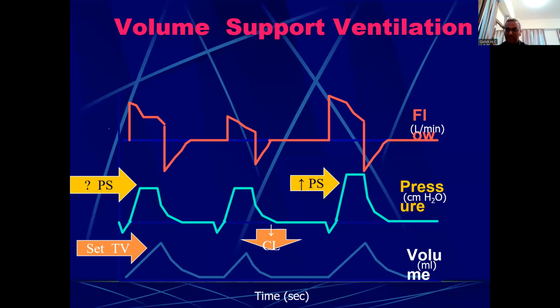It is sort of a self-weaning mode. It will keep changing the pressure support depending on the patient's compliance. So that is a big difference between volume support and pressure support. But both of them actually give pressure support only, whereas volume support assures a certain tidal volume. That's why it is also called volume guarantee ventilation in certain ventilators. It is the same as volume support ventilation.